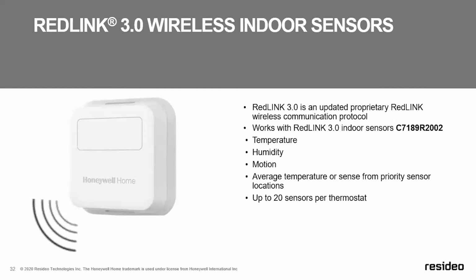The RedLINK 3.0 wireless indoor sensor that comes included in the T10 kit is a terrific option to provide more custom comfort inside your homes. This sensor senses temperature and humidity and has the ability to use motion to decide when that's added into your average temperature or becomes your room sensor. Up to 20 sensors can be used for creating a real custom sensing capability inside the homes that you are working in.